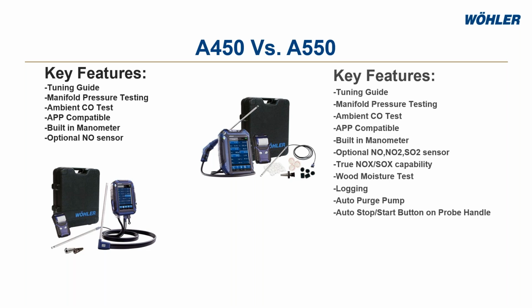You're going to have a logging feature. If you need to do continuous testing over time, the A550 gives you the logging capability to see and capture your readings over a certain amount of time. We'll get into more of these features as we go along, but I wanted to point out the key features each analyzer has. With the A550, you also have the auto purge pump, and some A550 kits have that button on the probe that stops and starts combustion testing.